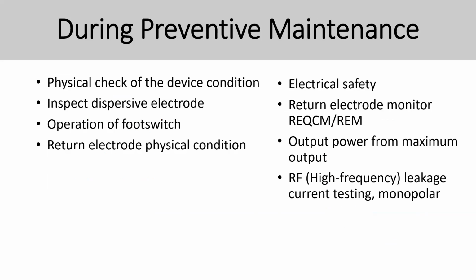So during preventive maintenance, the first thing you're going to do is a physical check of the device condition. I think earlier Musoma did mention all this, but we're going to repeat it. Inspection of the dispersive electrode, so you're talking about the patient return electrodes. You have to check, because most of the time what I see is that the cables are broken, and sometimes it still functions, but it's not going to function properly. Then the operating foot switch and the return electrode physical condition. So these are on the physical part.